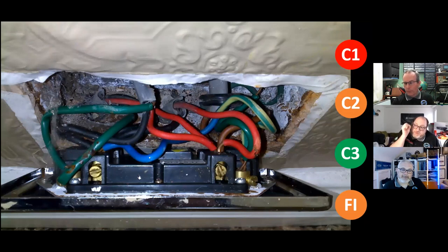It's for reasons like this why a lot of electricians just sample the bare minimum, because they'll lower that and then those little cables will come out, and technically, eureka, you found a problem, but then they've got to either fix it or put in all the pain and effort that the guy who originally put it in had to do as well. How many times have you had a pair of pin nose pliers and you've been trying to push that cable back in, where they're too short, because the person before you also did that and didn't tell you not to take that socket down ever again. Long nose pliers. Yeah. I shed a tear when I see them. So straight away, just playing devil's advocate here, while everybody's, if you could do a code on this. Yep. And then the lug breaks. Yeah. Jesus.